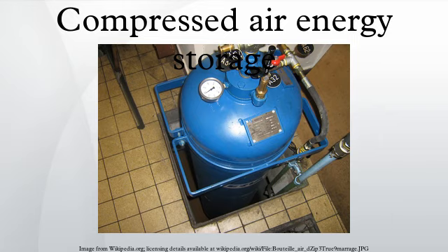Large-scale applications must conserve the heat energy associated with compressing air. Dissipating heat lowers the energy efficiency of the storage system. Types: compression of air creates heat. The air is warmer after compression. Expansion requires heat. If no extra heat is added, the air will be much colder after expansion. If the heat generated during compression can be stored and used during expansion, the efficiency of the storage improves considerably.